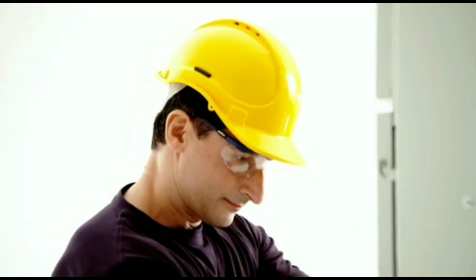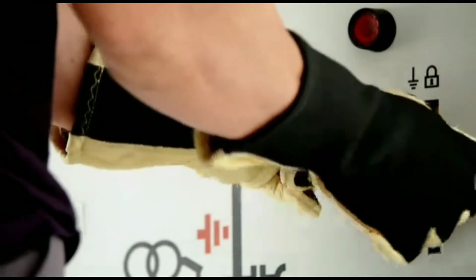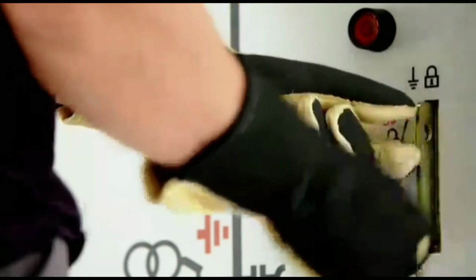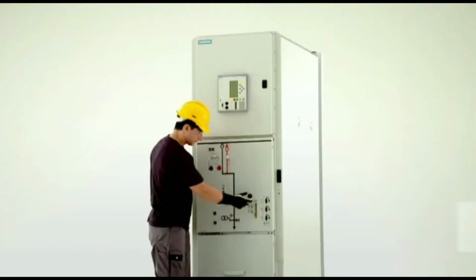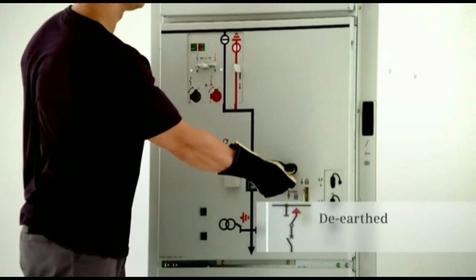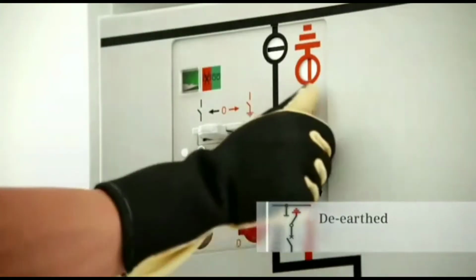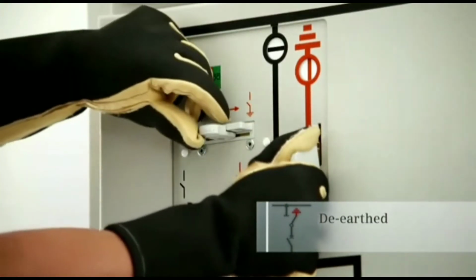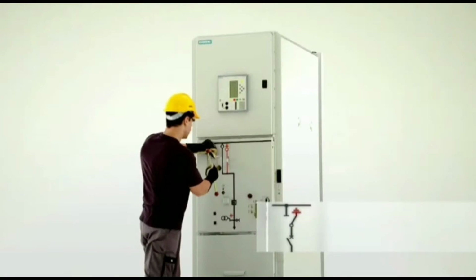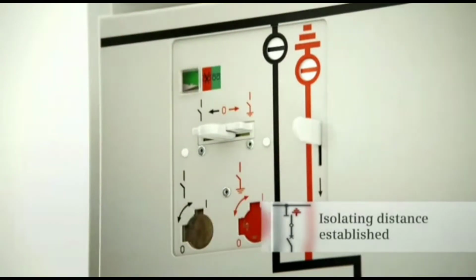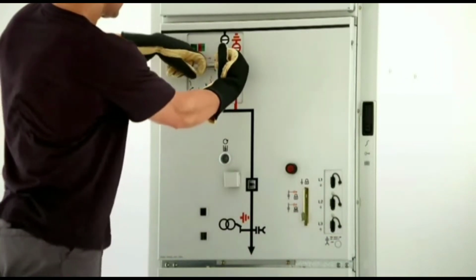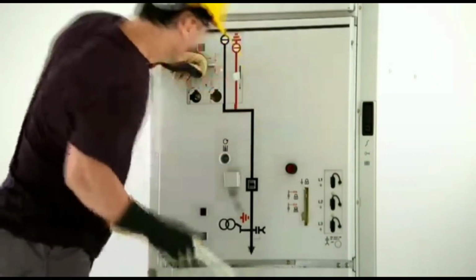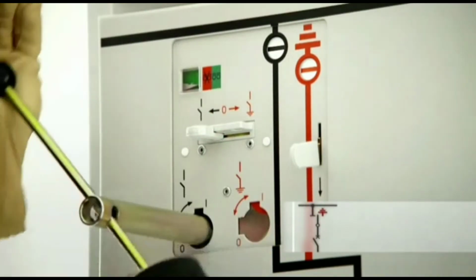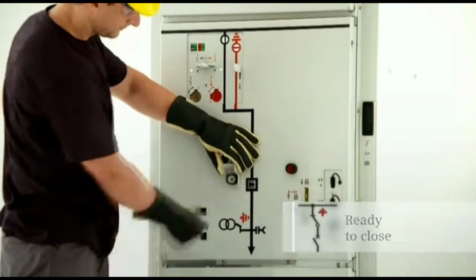To de-earth this feeder, the padlock must first be removed, rendering the locking device inoperative. The circuit breaker can then be switched to the open position and hence the feeder can be de-earthed. The three-position disconnector can then be switched from the ready-to-earth position to the open position and then to the closed position. The feeder is re-energized by closing the circuit breaker.